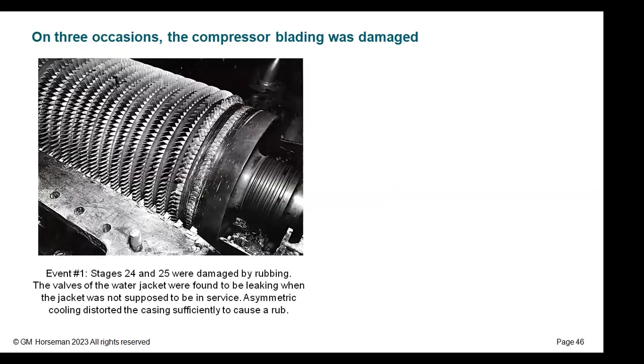There were 3 occasions when the compressor blading was damaged. The first one, you can see some of the blades at the outlet end, stage 25, have been knocked off. What happened here was there was a run where the water jacket was supposed to be out of service. Somebody left the water flowing slightly. So instead of filling the jacket completely with water, there was a little river of water at the bottom. So the casing was cooled asymmetrically and it distorted. And it rubbed the blades.